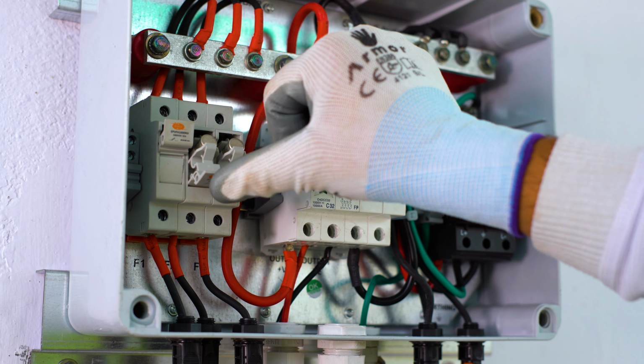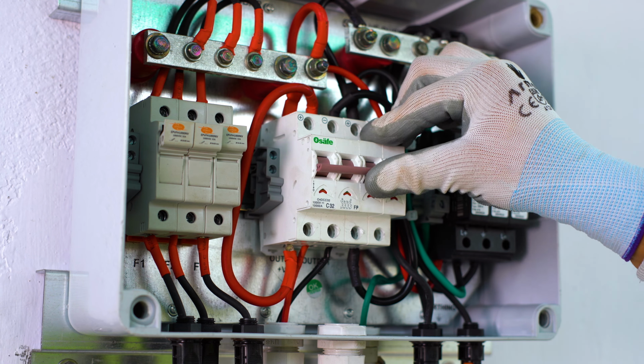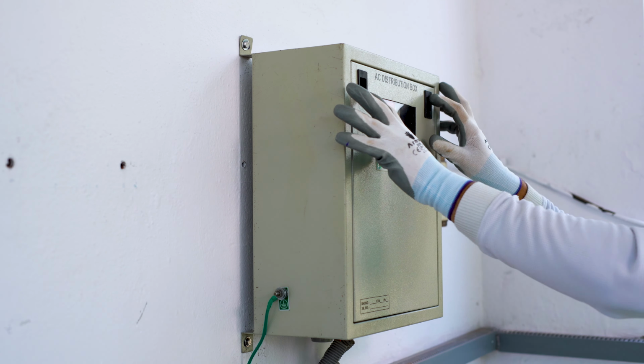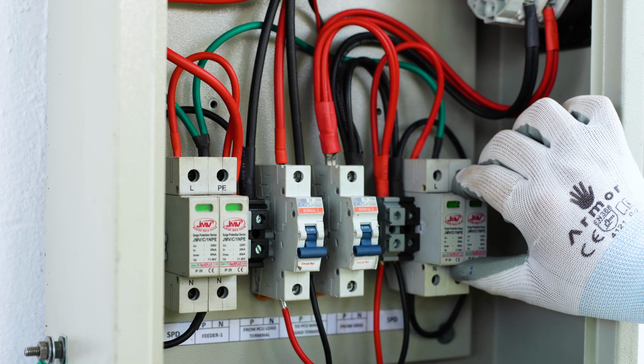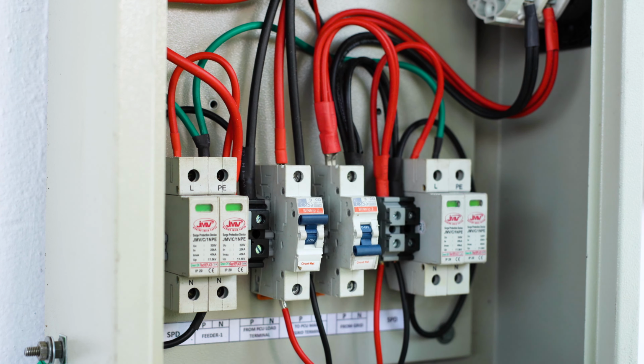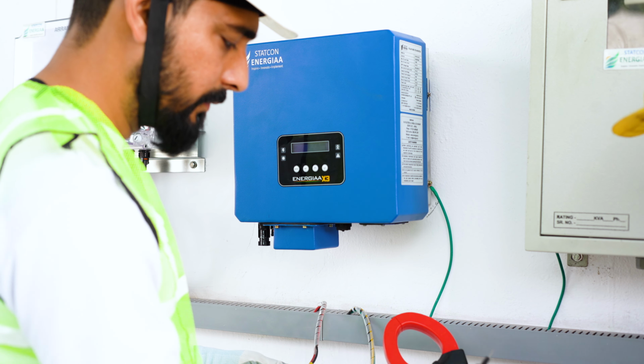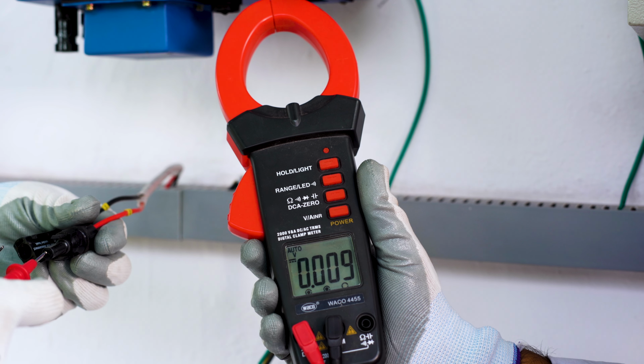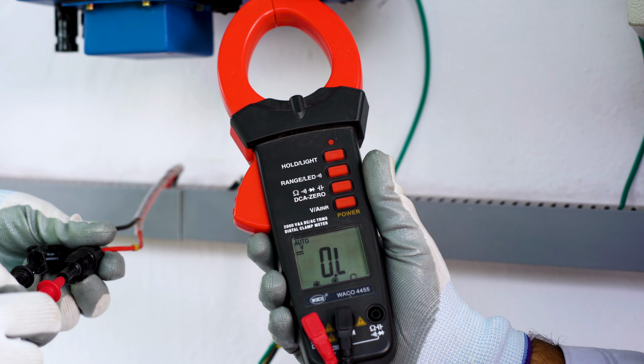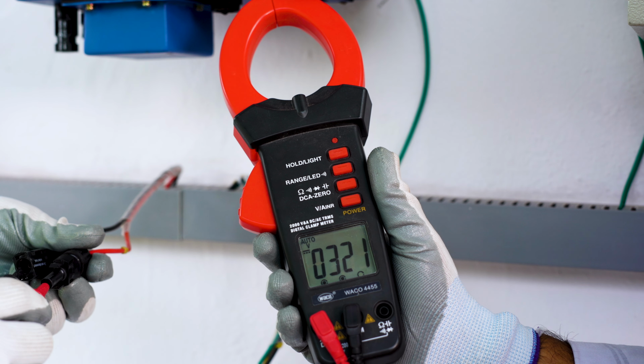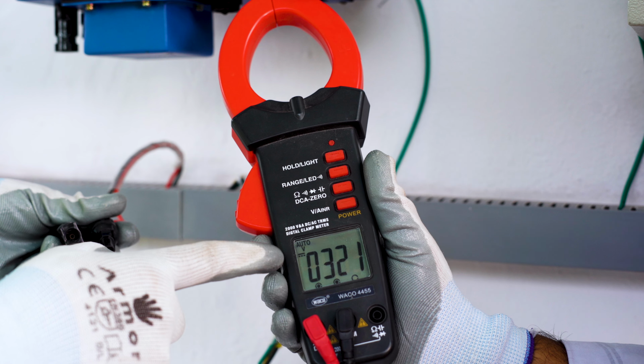To check the solar DC voltage, switch on the MCB in the AJB. To check the AC voltage, switch on the MCB in the ACDB. To check the solar string DC voltage, put the black probe in the black wire and the red probe in the red wire. The DC voltage is visible on the display of the multimeter.